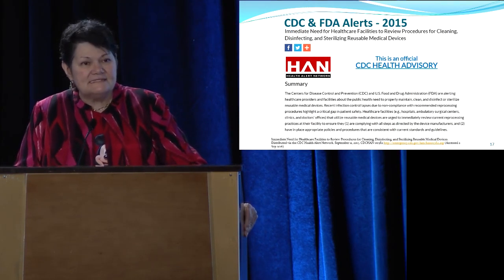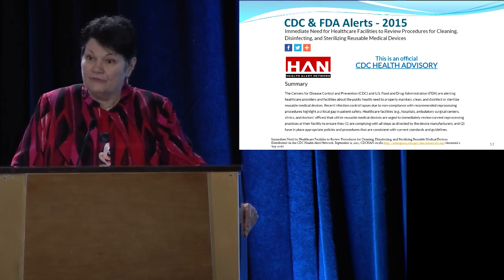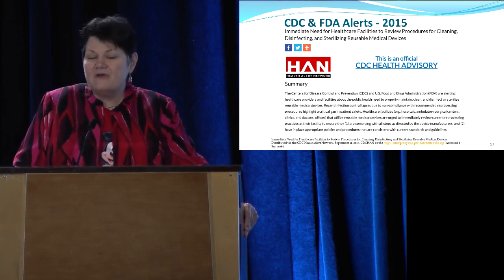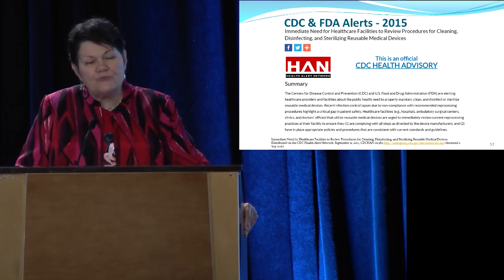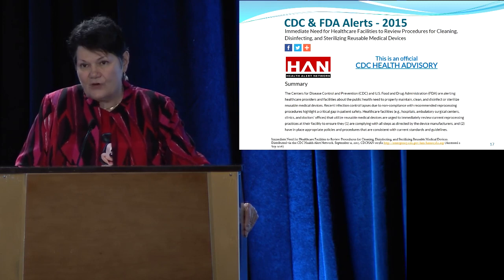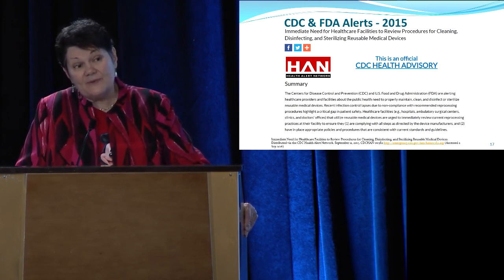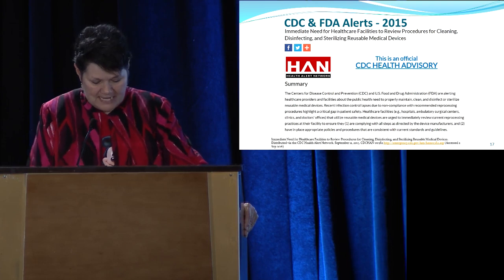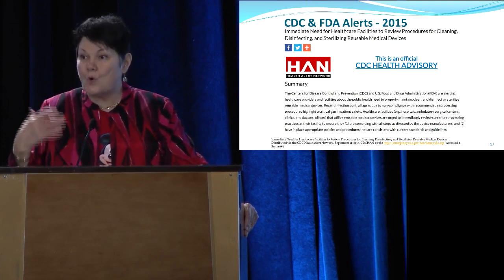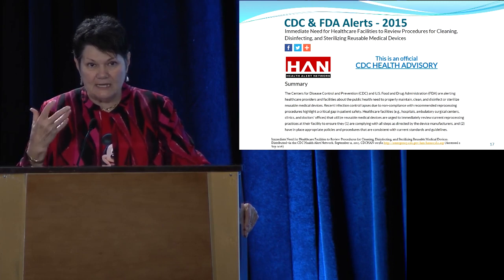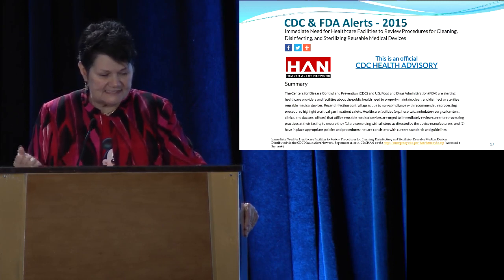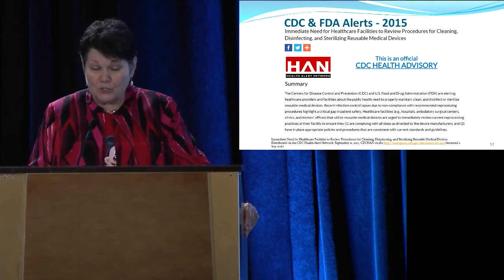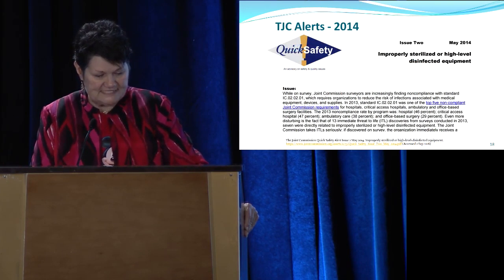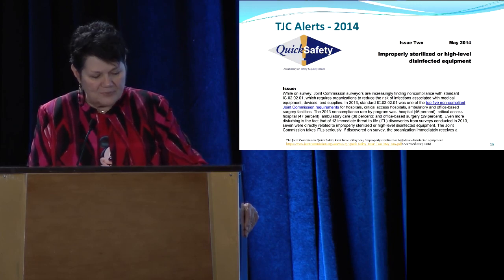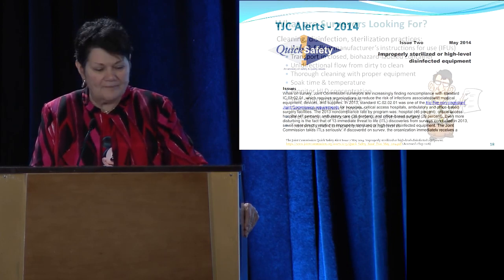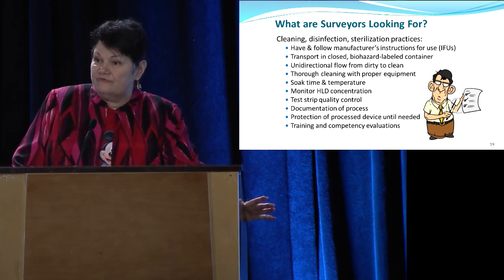So I mentioned that the CDC and the FDA put out a health alert from the Health Alert Network back in 2015 to have facilities review their policies and procedures and processes for high-level disinfection, and that they were following the Spalding criteria that we've talked about, because they were seeing so many lapses and failures in their surveys and things that CDC was doing. And the Joint Commission also had put out an alert previously in 2014 as well on improperly sterilized or high-level disinfected equipment. So what are surveyors looking for?